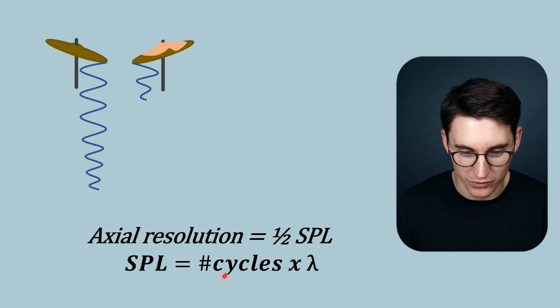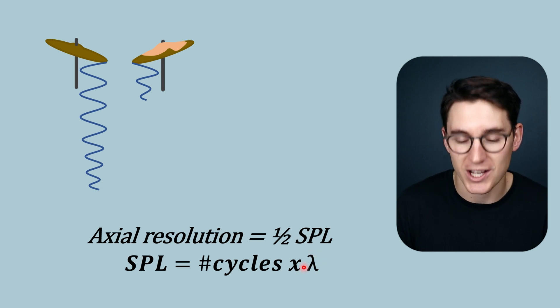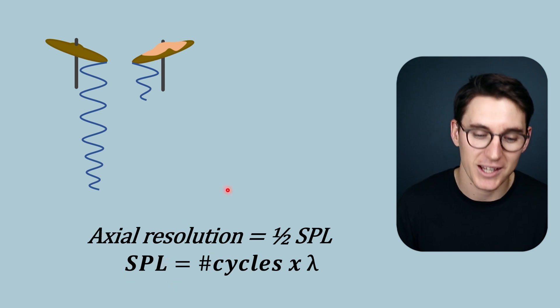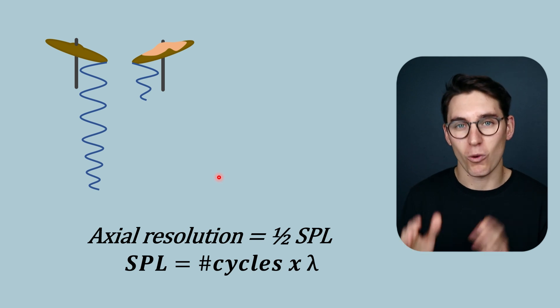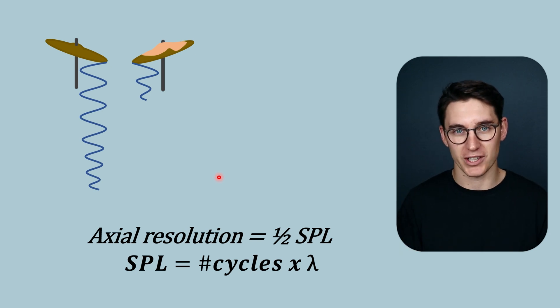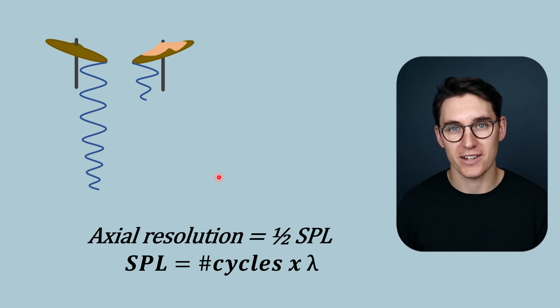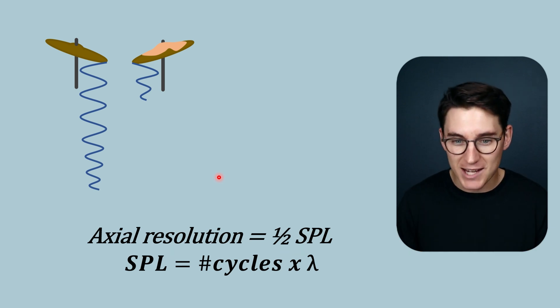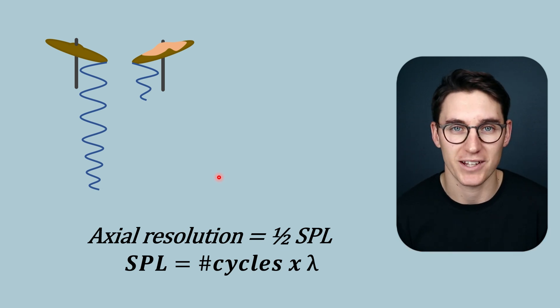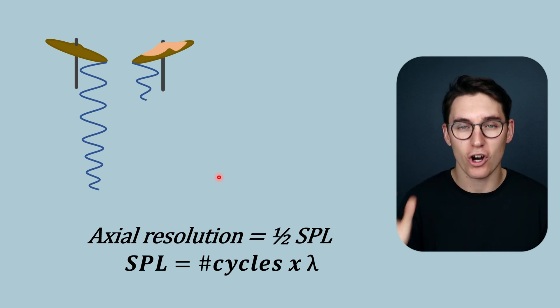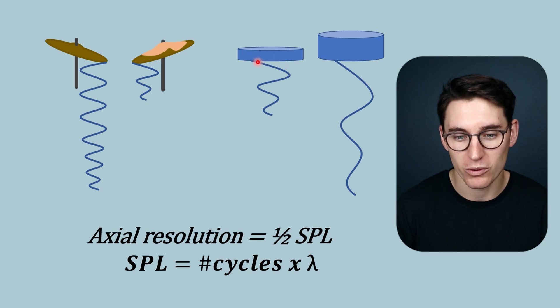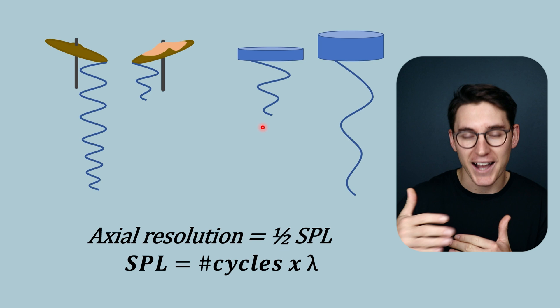The second thing we can do is reduce the wavelength — making our wavelength shorter reduces the spatial pulse length and ultimately improves axial resolution. Our wavelength is related to the thickness of the piezoelectric material. Just as the length of a guitar string is half the wavelength of the wave produced when plucked, the thickness of the piezoelectric material is half the wavelength it produces. Therefore, a thinner piezoelectric material results in shorter wavelengths and subsequently higher frequencies.